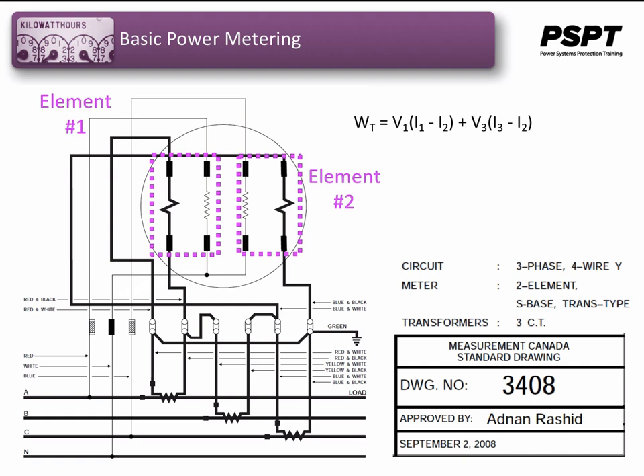Now, this type of metering, both with the socket base and the A-base meter using 3 CTs, and then manipulating the current so that you can subtract one from the other, is easy to do if you have current transformers, and they allow you to do this. If you did not have current transformers, in other words, if you had a direct connected watt meter, you could not connect the currents together. You couldn't make up I1 minus I2 because you would have to connect the primary phases together, which would short circuit them and it just wouldn't work.